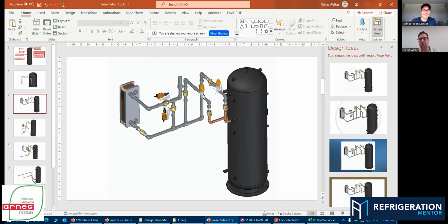Love that. So what we're doing is we're allowing these valves to properly work as well, because what we don't want in certain applications is ever the control system to start permanently closing these valves and work more like a holdback valve or like a Flowcon A8 valve. They weren't made to do that. And when we start cutting off these valves because mass flow is so low, we start losing that pressure differential in the system, right? But isn't that what most systems are doing at this point? Especially when you don't have this type of design, when it gets really cold, they are acting as that holdback.